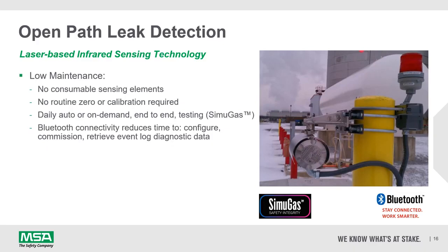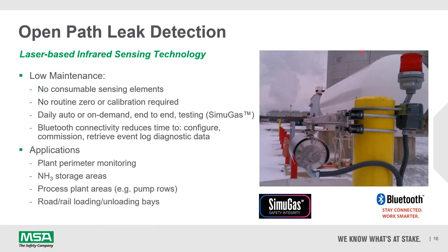Laser-based open path gas detectors are also low in maintenance. They have no consumable sensing elements. They have an auto-zeroing technique, along with being factory calibrated for life, requiring therefore no routine calibration. In terms of testing, there is a daily, automatic or on-demand end-to-end self-test facility called Simugas, negating the need for routine in-field testing. When accessing the unit, Bluetooth connectivity also reduces the time to configure and retrieve event logs for fault diagnostic purposes. So the applications typically include perimeter monitoring, NH3 storage areas, such as the picture you can see on the right of a unit perimeter monitoring an ammonia vessel, process plant areas, road and rail loading areas.